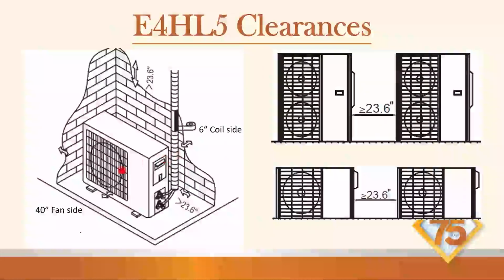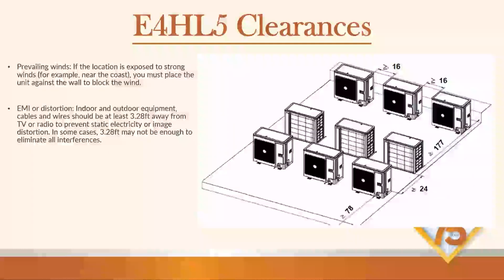6 inches from the exterior, 40-inch to the fan side. So it's a little bit different. They want 40-inch from the fan side. I'd always say 2 foot from the electrical. And that's showing that too. So if you have 2 side by side, it wants 23.6. Round it up, keep it 24 inches. There's some nice illustrations if you have multiple sitting on the roof or some kind of condominium.